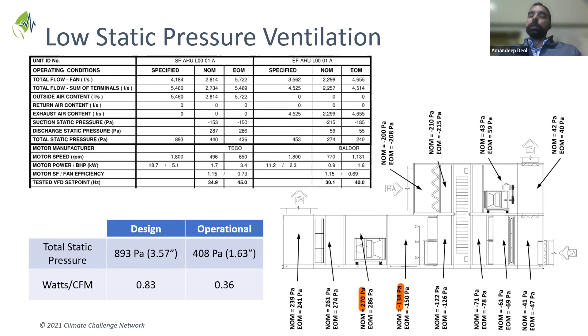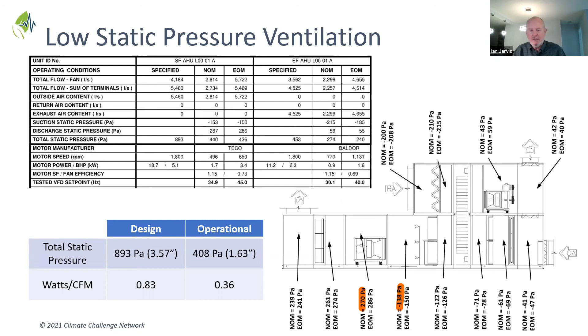And this is a significantly lower static pressure than you would expect on these units. And I think the contribution, and Kurt can add to this, is because of this oversized ventilation system that's been designed in this hospital as part of the original design intent, which is what's been helping the hospital achieve those substantial fan power reduction numbers. Yeah, we'll come back to Kurt in just a moment on all of this. And Kurt, if you could summarize what were the big deals, and within that, what were the challenges in moving things through. But the other features you picked up, Andy.